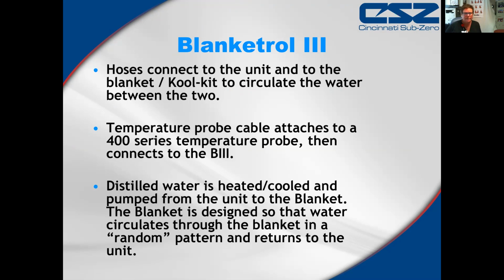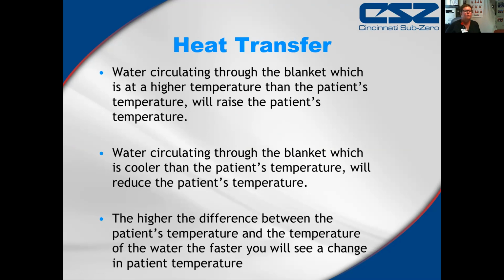When we begin to use the blanket, we also put distilled water into the back of the machine, and I'll show you that at a later date. So heat or cool is transferred through the blanket that we use. And so I encourage you, if you have the ability on your machine, to use 2 blankets at one time. And this Blanketrol III actually has 3 connections, so you can use 3 sources of transfer. So a blanket below the patient and a blanket above the patient are really what's recommended, and will bring you to target temperature the most effective way, or the quickest way.